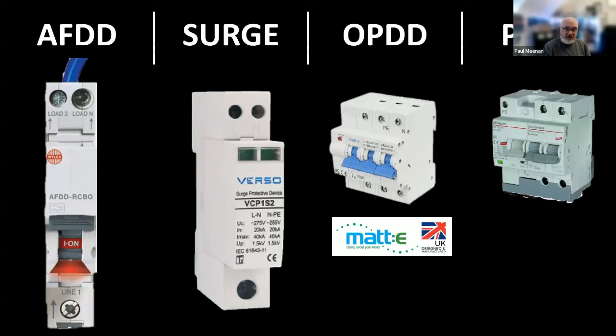But when we're on that journey of selection and erection of our protective devices, we're now in a world in England where we have an arc fault detection device to BS EN 62606. We have surge protection to protect against atmospheric strikes and strokes. Strikes being a direct strike, stroke being the after effect, where you could get transients of thousands of volts. And we then do staged protection to ensure that any voltage spike within the installation dissipates and is protected and connected to earth. So there's a device that's essential to earth.